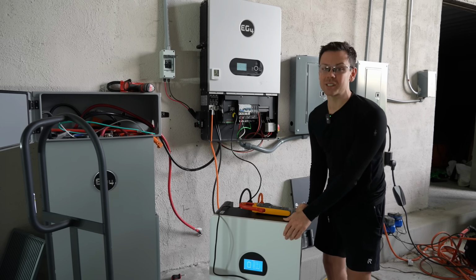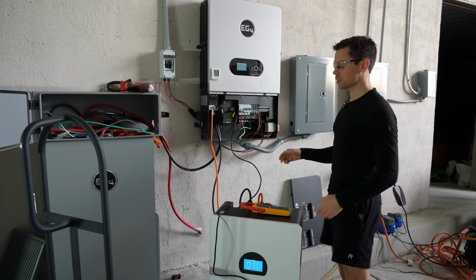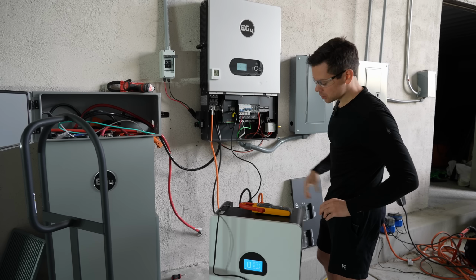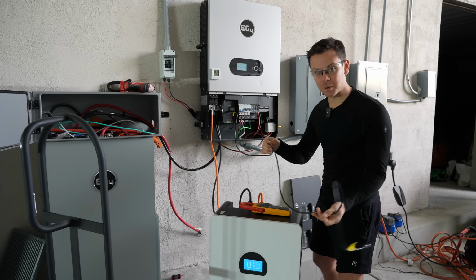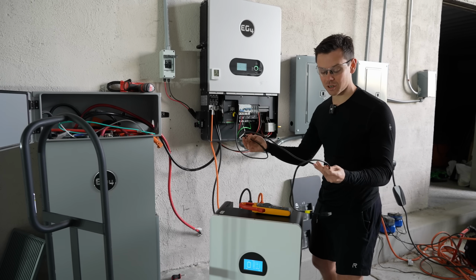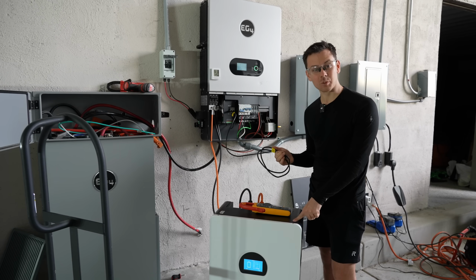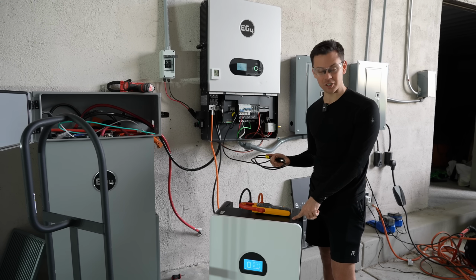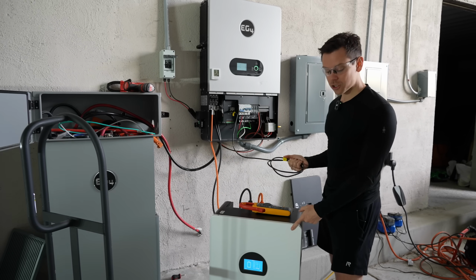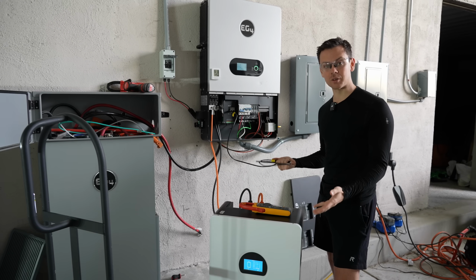That's not good. Now it hit 47 volts and it's dropping rapidly, so let's turn this thing off. And the lowest I could get was 6% state of charge. Now let's turn on solar and charge it. So it works, but this communication cable is giving the wrong signal on state of charge, which is strange because this should reset after every cycle. It shouldn't have this problem.